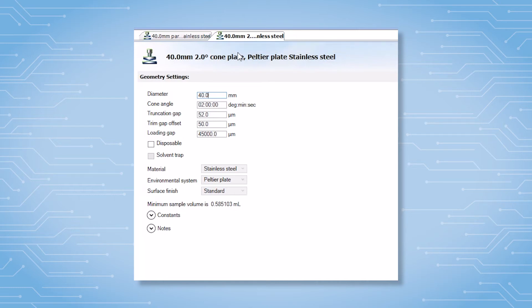During temperature ramps, the geometries expand as the temperature increases based on the coefficient of thermal expansion. Parallel plates are preferred in this case because they can be operated at a variety of gaps. The operating gap for cones is the specified truncation gap, which is much smaller than the parallel plate gap, so small deviations in the gap height can cause significant errors.